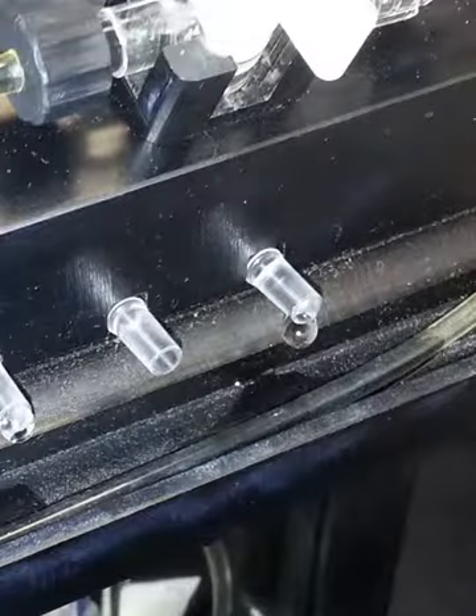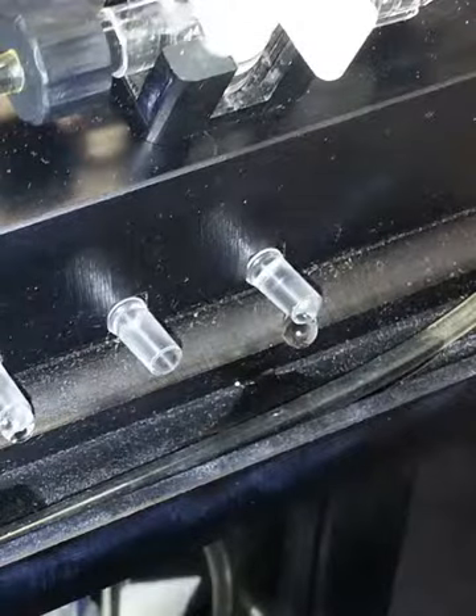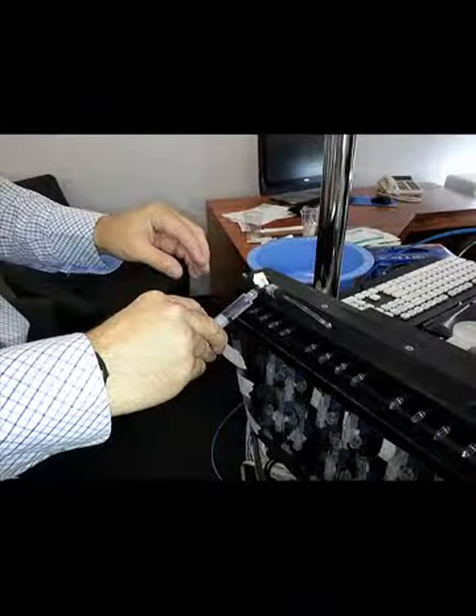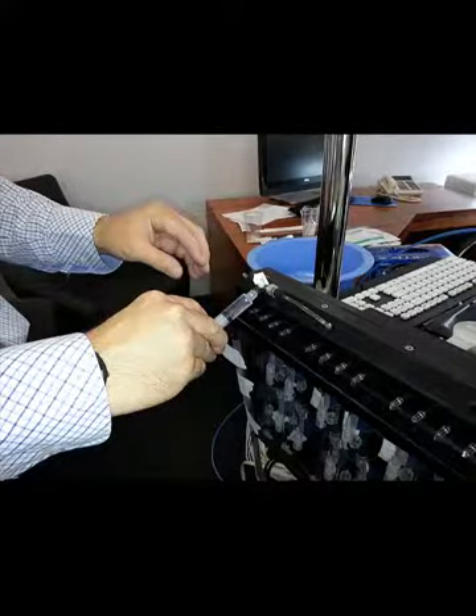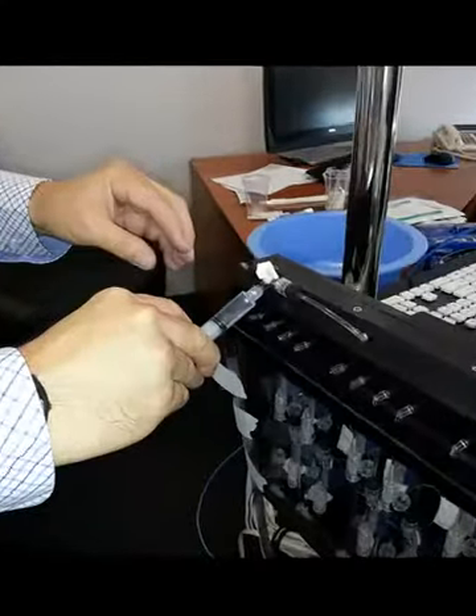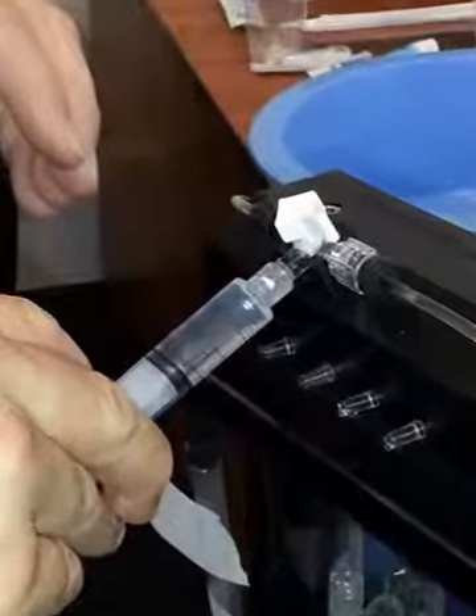If one channel is not dripping and the transducer chamber is not filled with water, the capillary is likely to be blocked by a microbubble. In this picture, the channel second from the right is not dripping. In order to deal with a blocked capillary, fill the 5 ml syringe from the water reservoir by turning the lever to the right and allowing the syringe to fill.